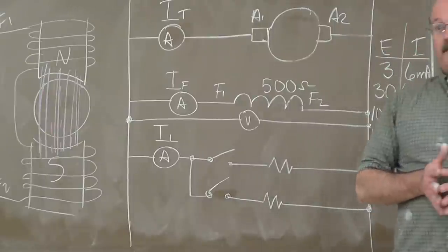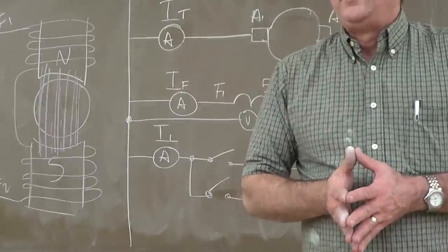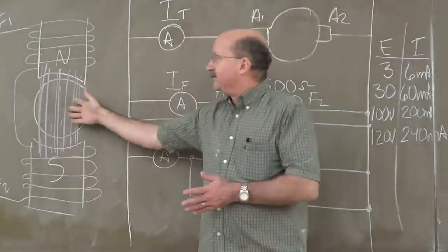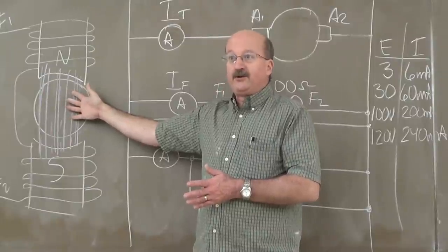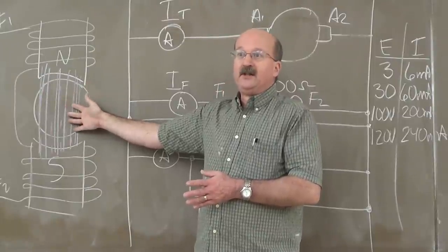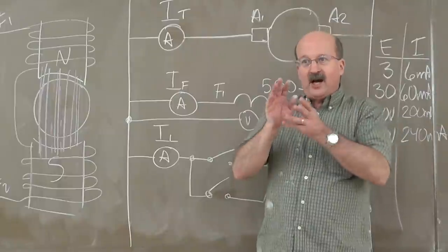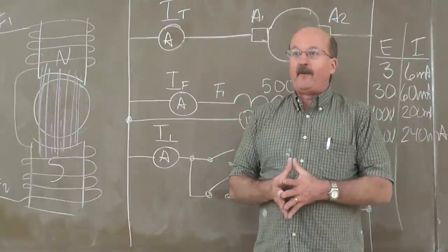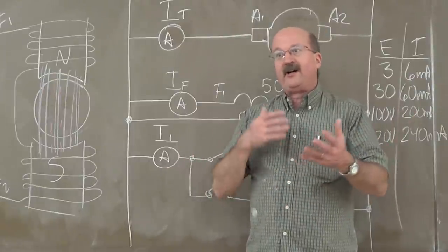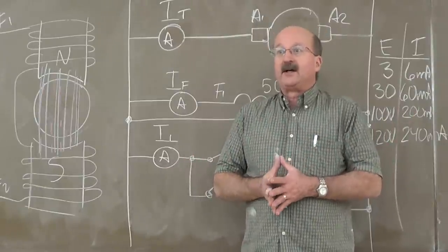Does the amount of magnetism you have to apply back to the armature stay the same for any size generator, or does it change? It will change by the generator, and the voltage that's generated due to residual magnetism will change with generators. We know that the Lab-Volt generators we're using have a nominal voltage with a residual magnetism of about 3 volts. If you have some other generator with different winding and different characteristics, it's going to be different.